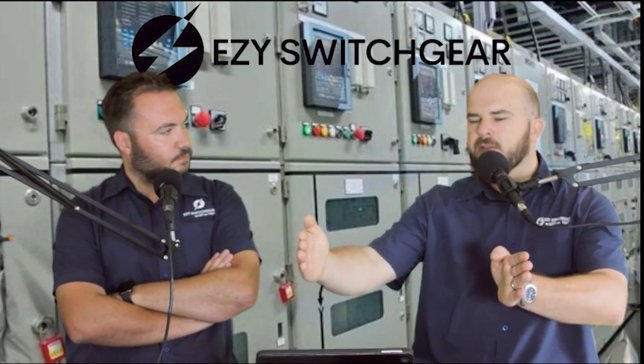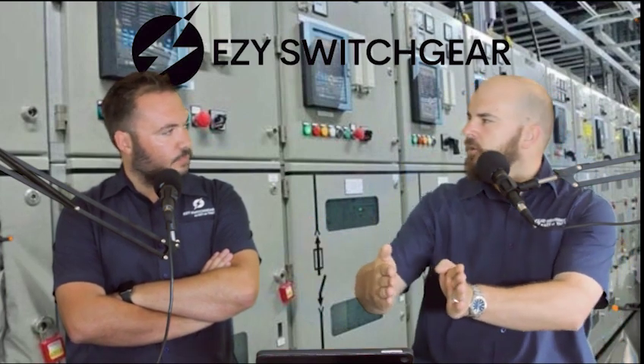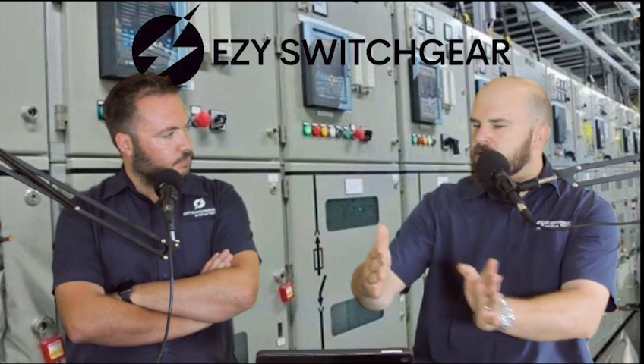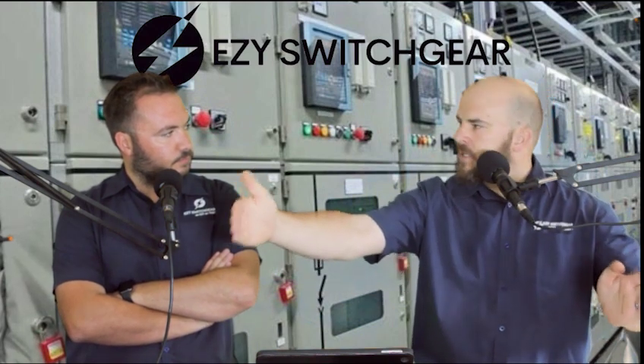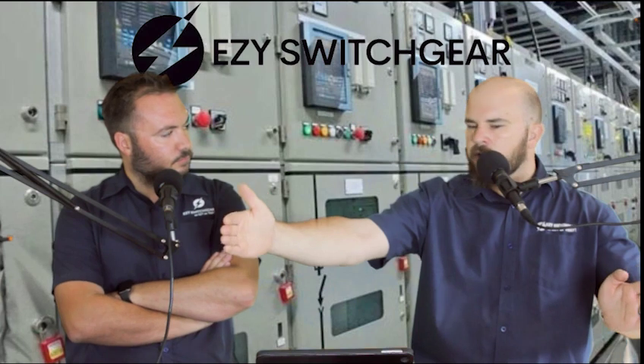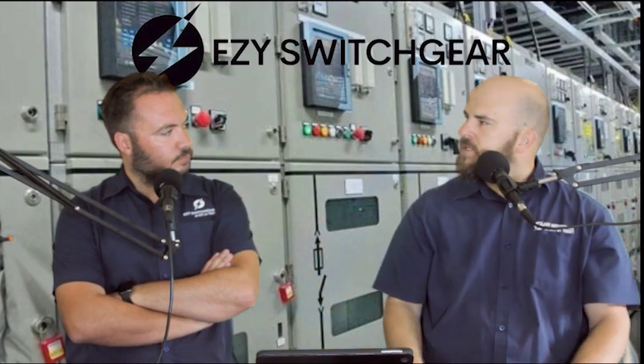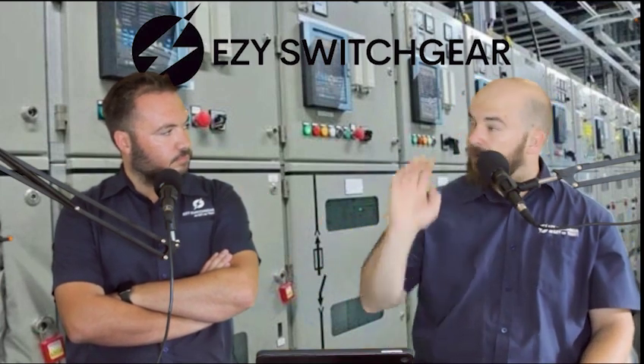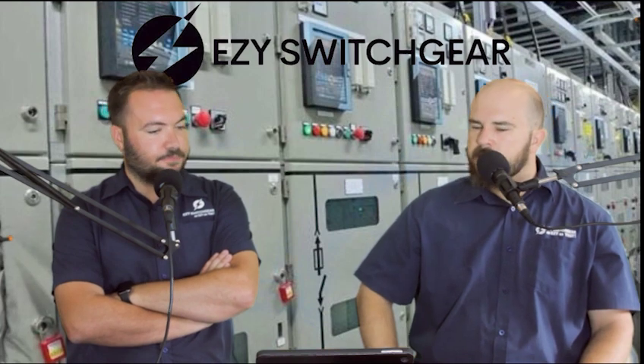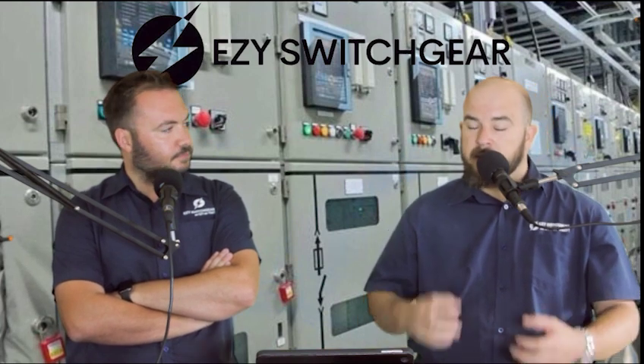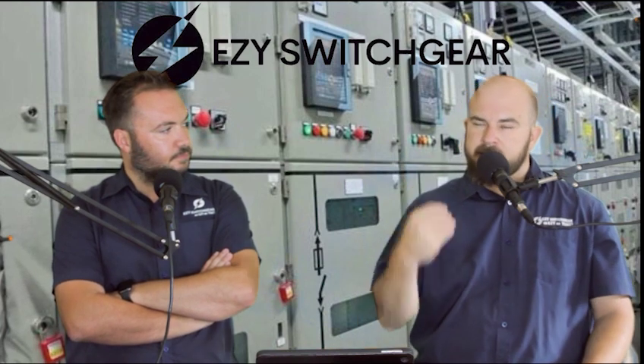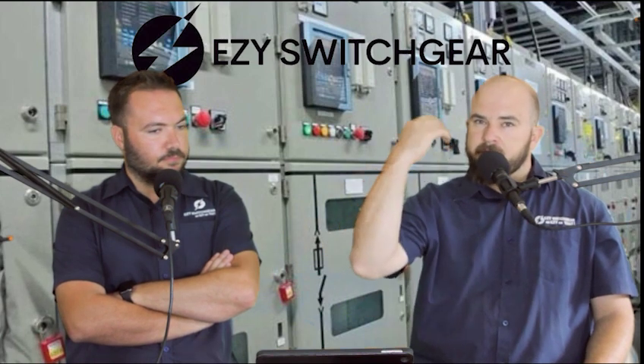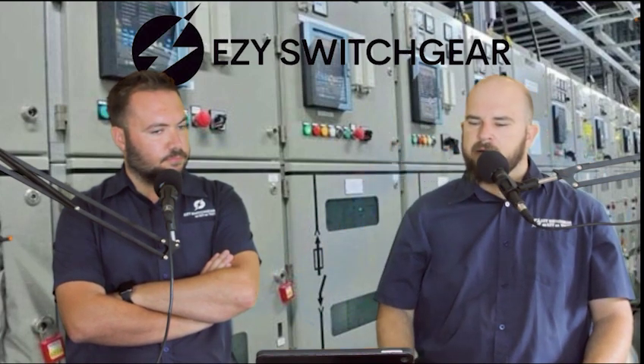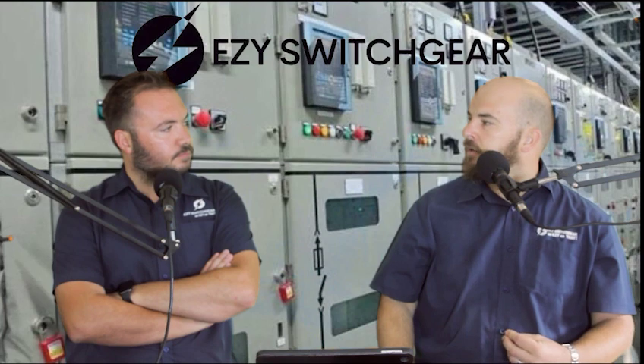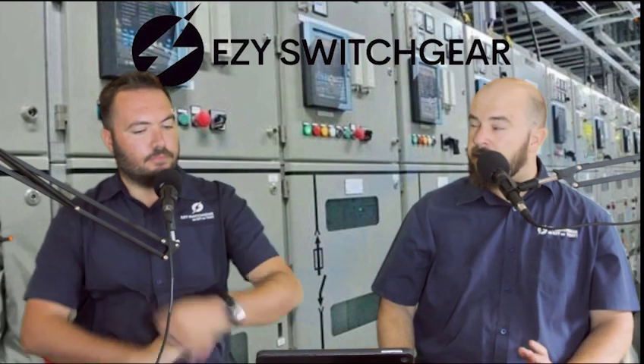So you can now bring it 6 times closer. You can literally bring it so close. So a panel that would be 600 millimeters wide, you can now squeeze into 360 millimeters for a 24 kV panel. Yeah, that's amazing. So gas insulated switchgear, that SF6 needs to be a very stable gas that lasts a very long time and will not break down easily. Yeah. So SF6 is very, very stable.